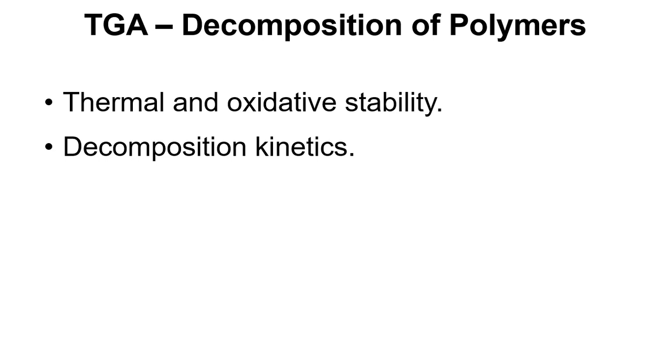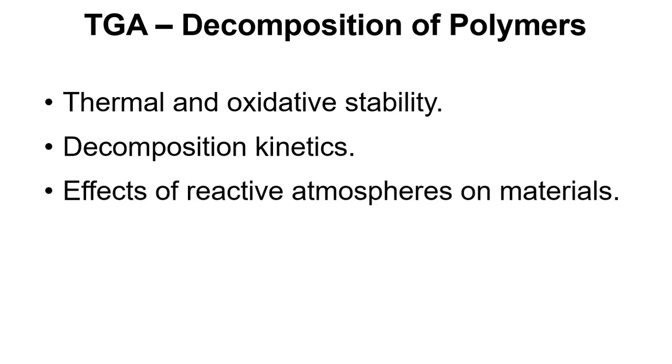We can look at decomposition kinetics. We can look at the effect of reactive atmospheres on our polymer. We can work out filler content, so any solid material in there that doesn't decompose that's been added to enhance the properties of the polymer.